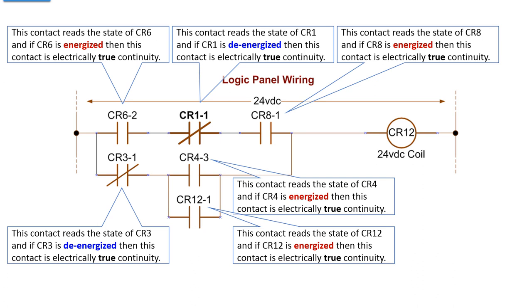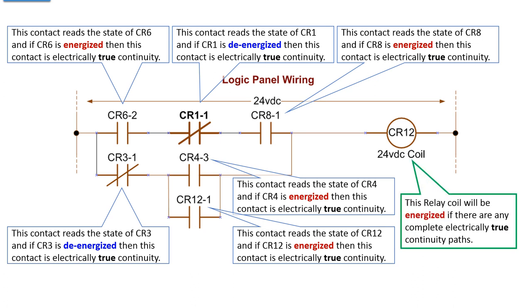These two, if CR4 and CR12 are energized, then you have electrical true continuity. Now notice that CR12-1 is a contact that's controlled by CR12. So if CR12 is energized, that closes this contact and bypasses CR4-3. Any logically true path through this set of contacts here will energize CR12.